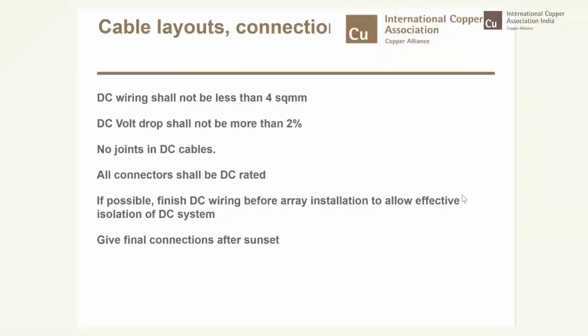Like cables are rated for 1000 volt. So appropriately, the connectors shall also become 1000 volt rated. The small tip here is, if possible, finish DC wiring before array installation to allow effective isolation of the DC system. You can finish your DC wiring and finally install and do the last interconnection after the sunset. So that will perfectly go ahead with considering the safety aspects.